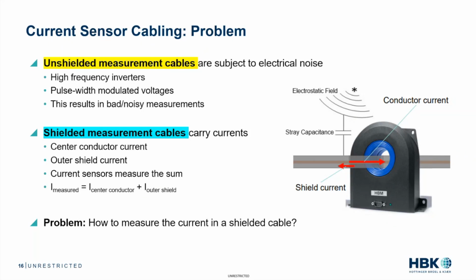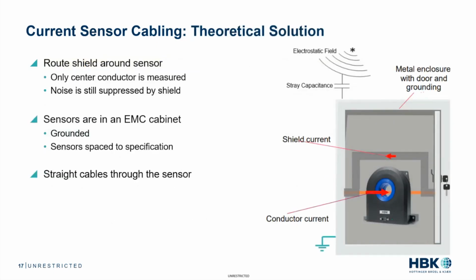And ideally, you want to measure the center conductor current, not the outer shield current. If you were to take the entire shielded cable and place it right through the CT, you'll end up measuring both the center conductor and the outer shield. So you ideally would want to avoid that circumstance, but how do you go about measuring just the current in a shielded cable? Well, here's one solution.